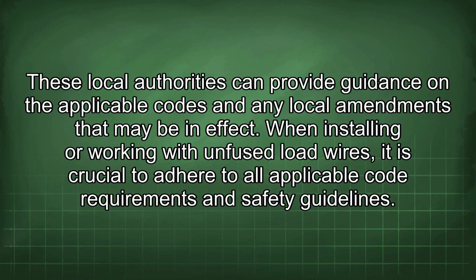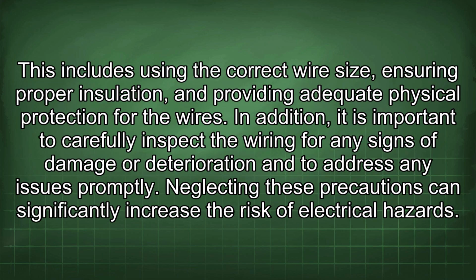When installing or working with unfused load wires, it is crucial to adhere to all applicable code requirements and safety guidelines. This includes using the correct wire size, ensuring proper insulation, and providing adequate physical protection for the wires. In addition, it is important to carefully inspect the wiring for any signs of damage or deterioration and to address any issues promptly. Neglecting these precautions can significantly increase the risk of electrical hazards.